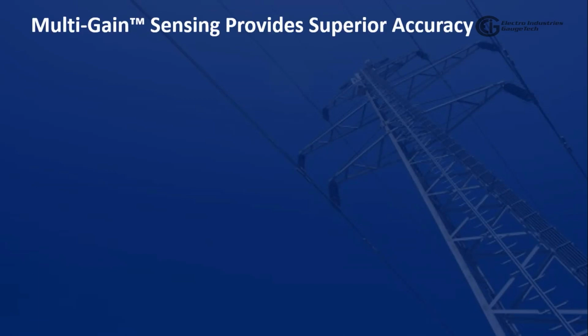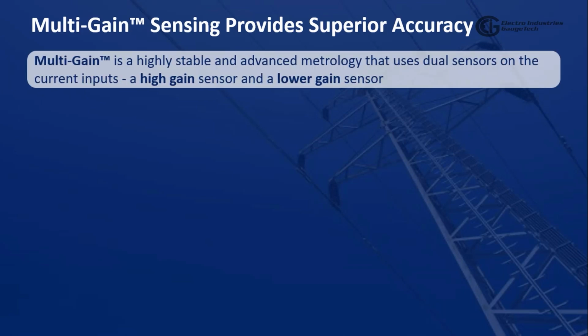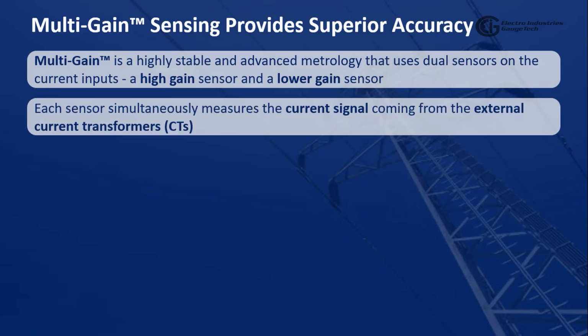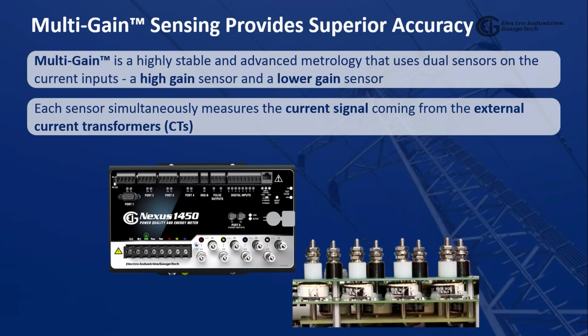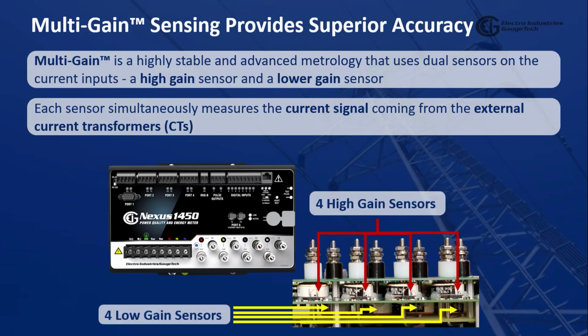At its core, the metering system utilizes multi-gain technology, which provides superior accuracy. This is a highly stable and advanced metrology that uses dual sensors on the current inputs, a high-gain sensor and a lower-gain sensor. Each sensor simultaneously measures the current signal coming from the external current transformers. If you look at the bottom view of the meter, you will notice that there are 4 high-gain sensors as well as 4 low-gain sensors.